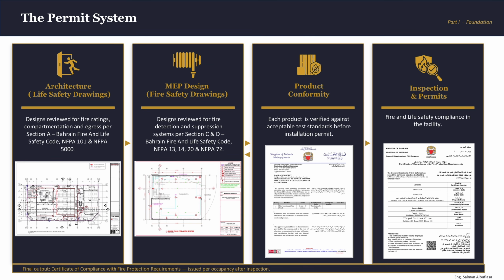And then we have the product conformity. What I say is the manufacturer catalog is not a proof. I can make one using Canva today, so it's not a claim. What proves the product actually works is testing against a recognized standard under controlled conditions by an accredited body with documented results. That tested and certified performance is what the approved layout is built around. Every calculation, every spacing, every coverage area. So when you change the product, the whole system no longer performs as designed.